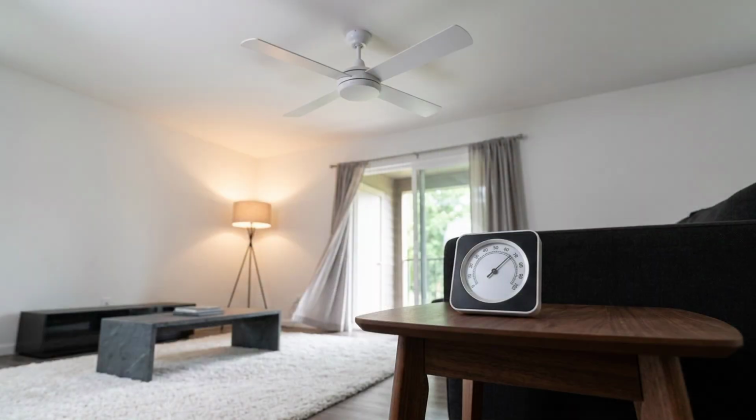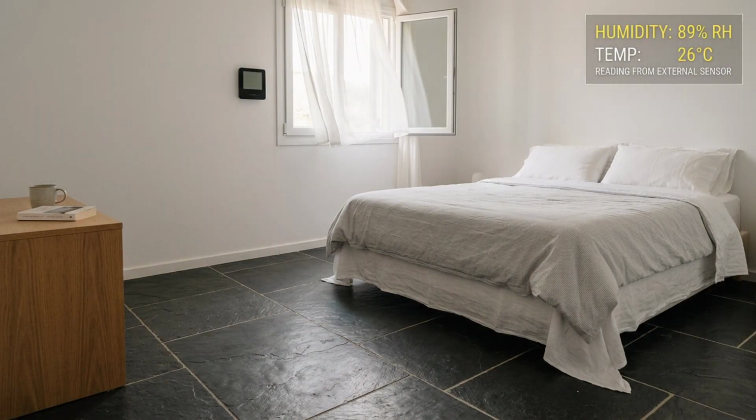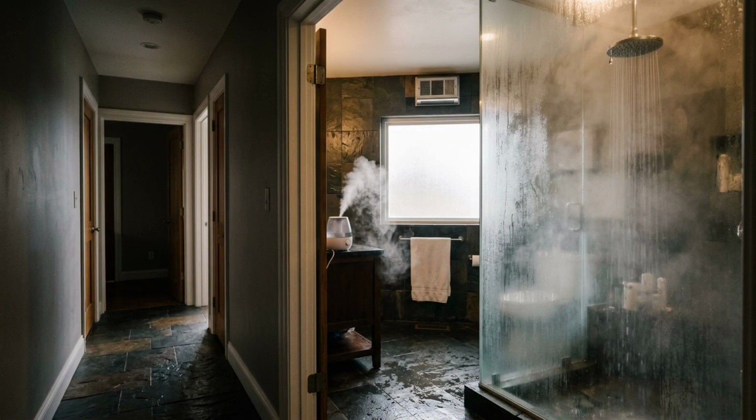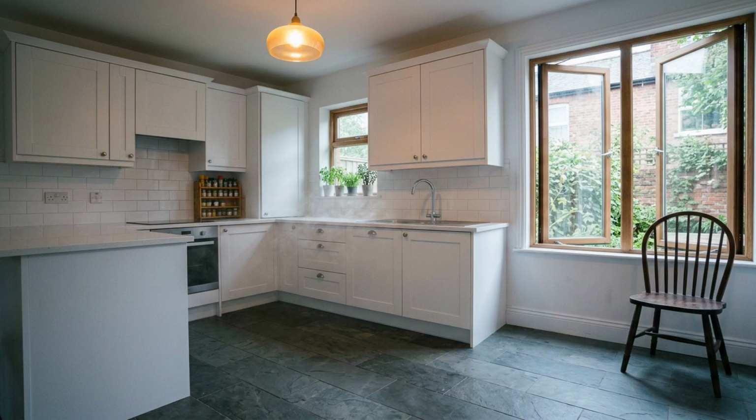Start with the meter itself. Record the temperature as well as the relative humidity. Record which room it is in and whether it sits beside a shower, humidifier, supply vent, cold window, open door, or other local source. A sensor answers the conditions at its location. It does not automatically represent the basement, bedroom, bathroom, wall cavity, and attic at the same moment.